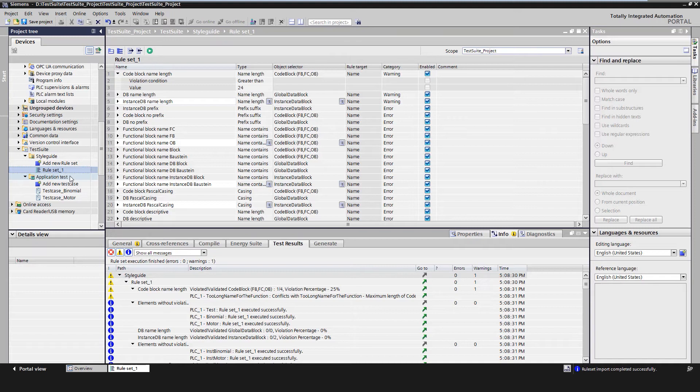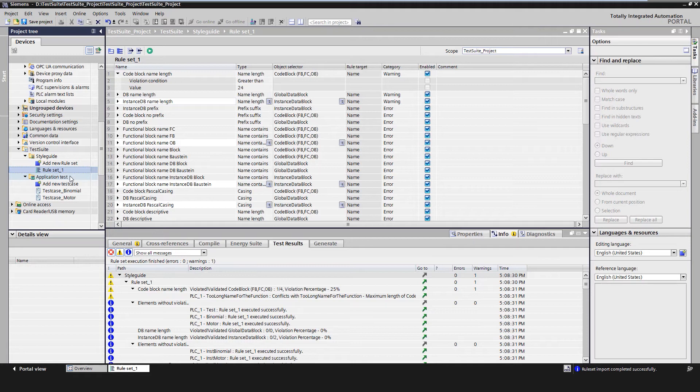A test step typically consists of the value assignment to PLC variables—the values required for the test, the execution instruction such as the number of CPU cycles or time. It also contains the test conditions under which the actual values are compared with the expected values and a message is generated.